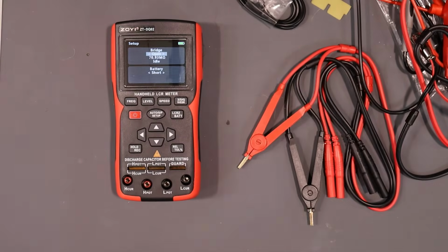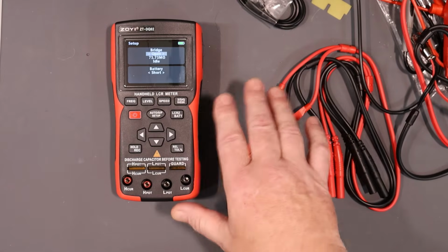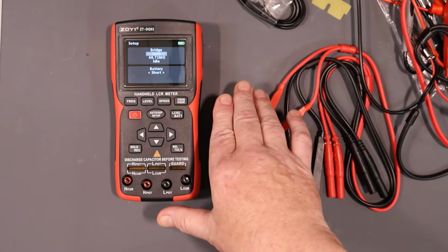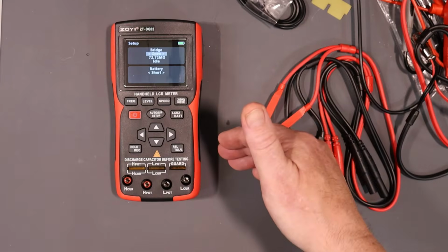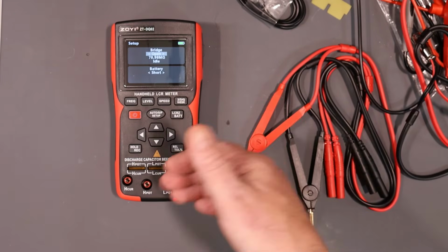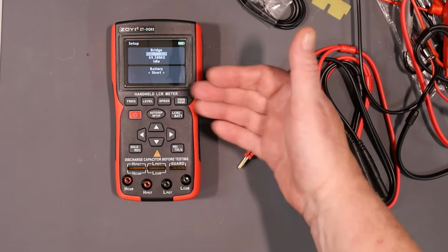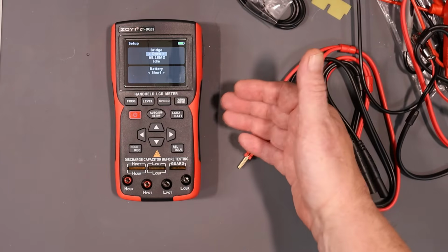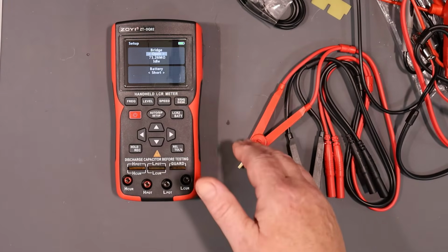I did contact Zoyi on this, and they said the only time you might ever have to do any of those resistance calibrations is if there's a firmware upgrade, and even then, only if you see a problem, and only do the 10 milliohm and 100 milliohm calibrations. The rest of them should not be required.